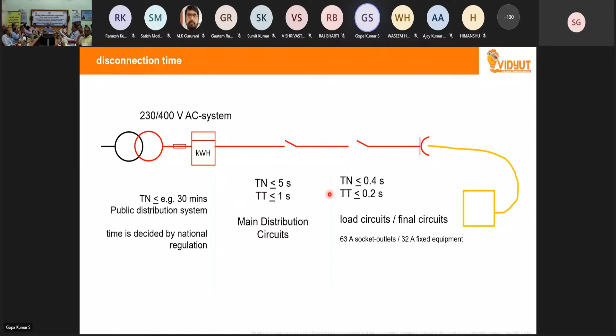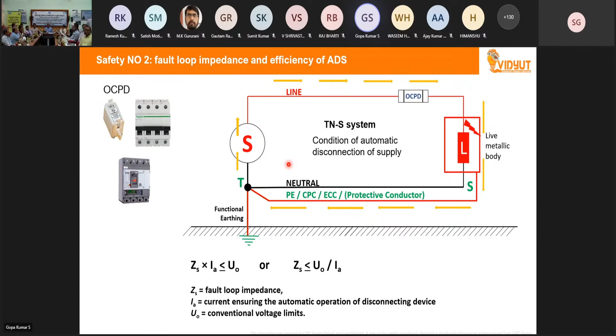What it means is, all metal parts in the building, be it application of low voltage, high voltage, extra high voltage, or whatever, must be interconnected in such a way that the person is not getting a shock. It is called protective equipotential bonding. So the correct safety measure is protective equipotential bonding and automatic disconnection of supply. For automatic disconnection, we use protective devices, and these have a parameter called fault loop impedance, with which the impedance of the circuit decides the disconnection time.